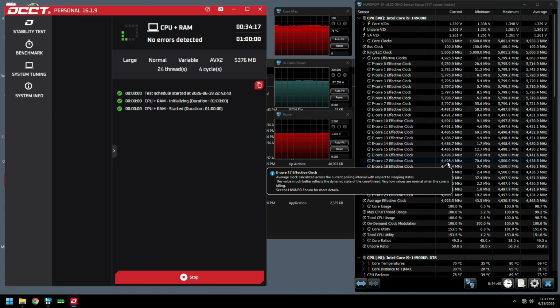So it's been 34 minutes. It's on its 4th cycle. Again, I would say the minimum you should run this is 3 cycles, and that takes about 30 minutes. I recommend running it for 5 cycles. So when the cycle here says 6, that takes about an hour, like 55 minutes.